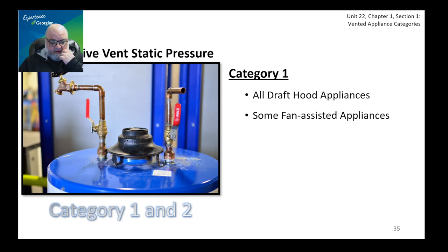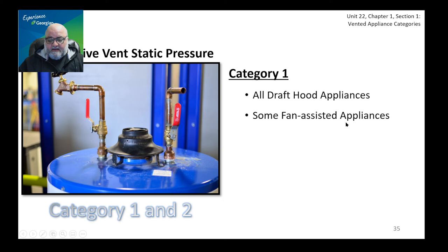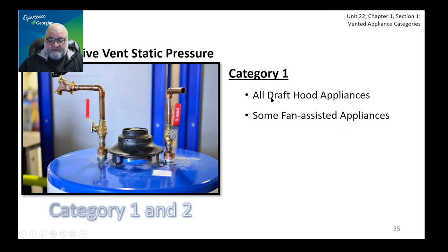For category one appliances, they all have draft hood appliances or fan-assisted appliances. In the codebook, Annex C says you size only category one appliances, and you have only two types: the draft hood appliance or the fan-assisted appliance. Category one will be either draft hood or fan-assisted appliances.